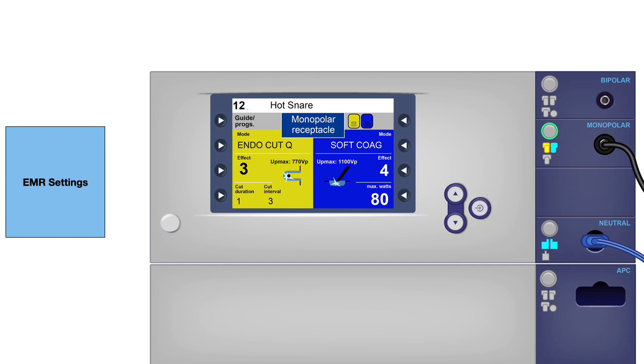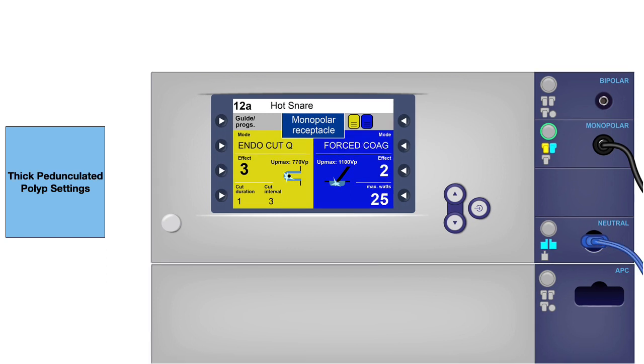So let me share with you what settings I use. My EMR settings typically are endocut Q 3 1 3, and I rarely change them. But recently I moved my forced coagulation to the soft coagulation setting, so that if I cut and end up with some bleeding, I'm not in the middle of asking my assistant to change from forced to soft coagulation. I don't want to waste the time. So instead, I've set these parameters. If there was bleeding, I could just tap on the blue pedal and deliver the soft coagulation.